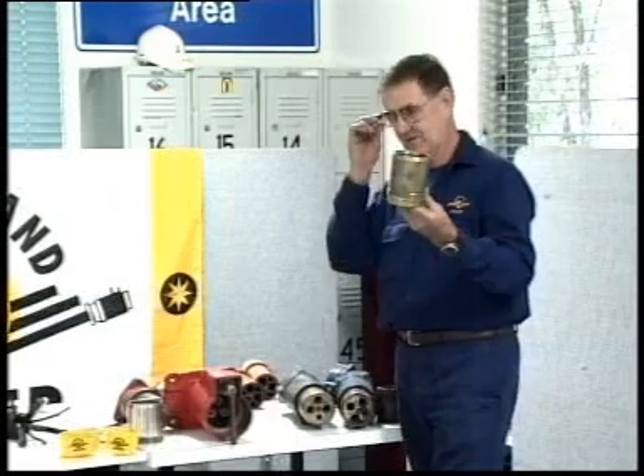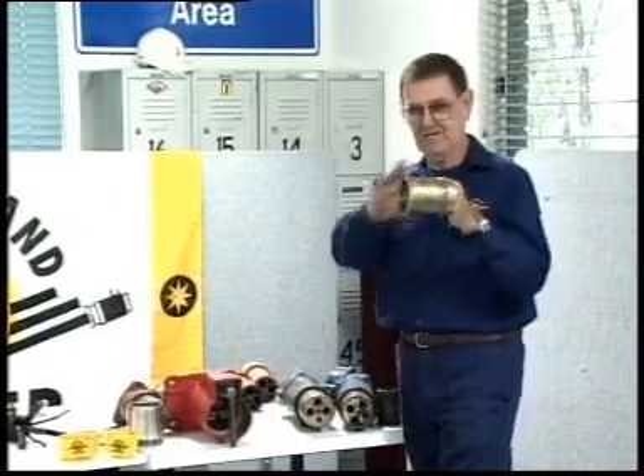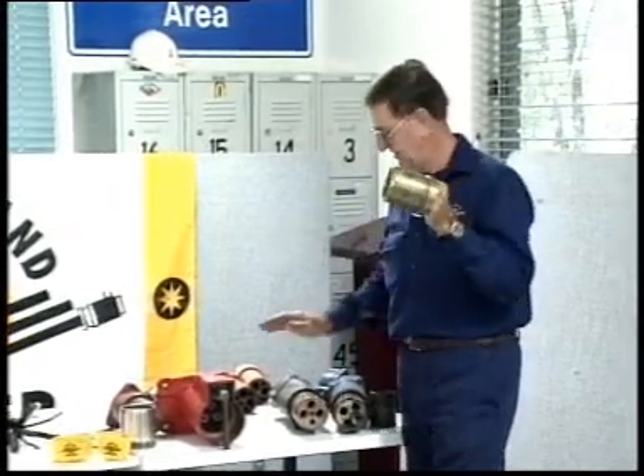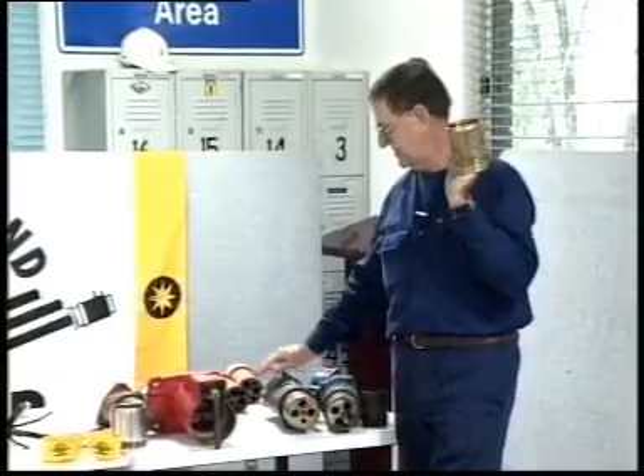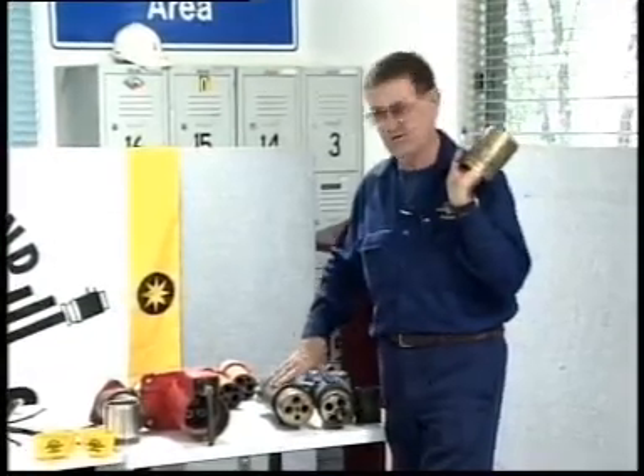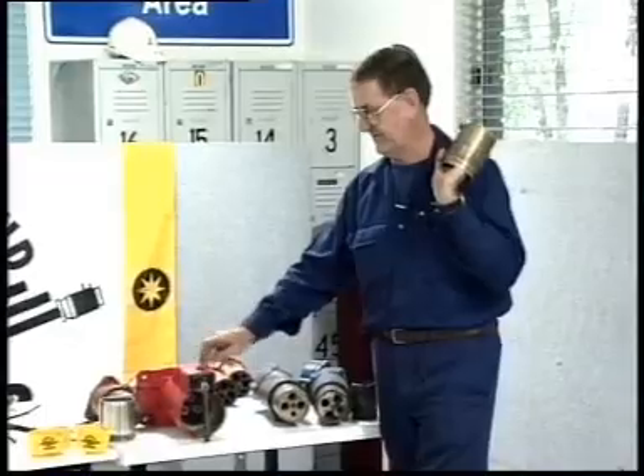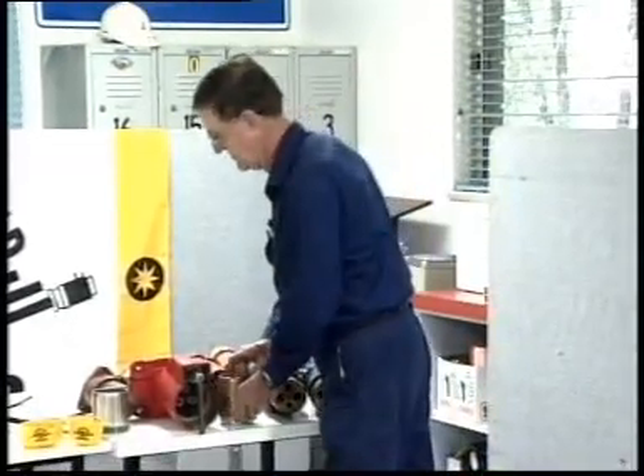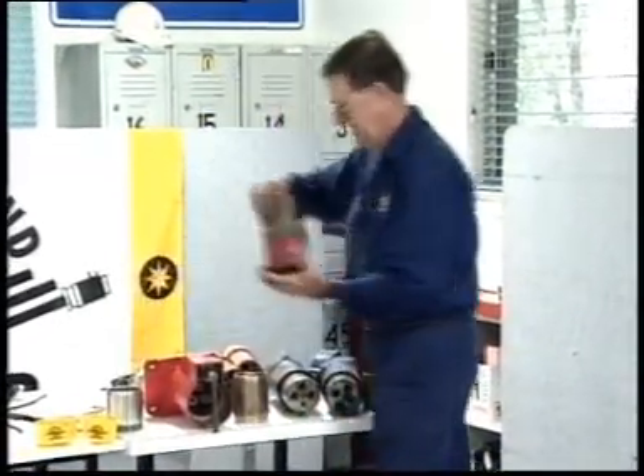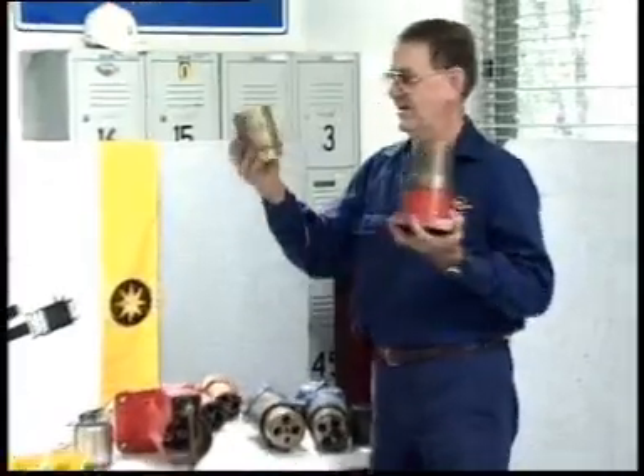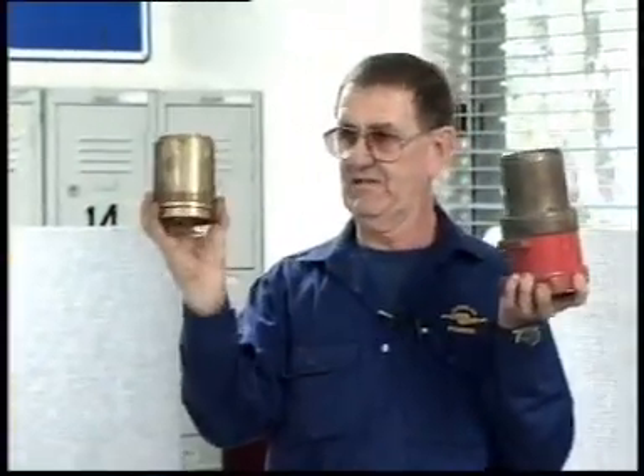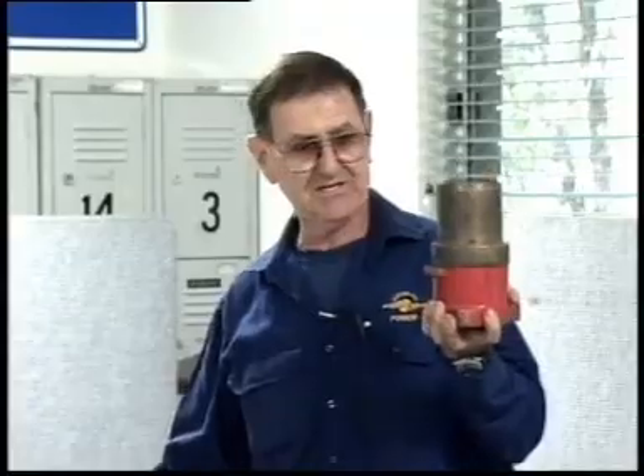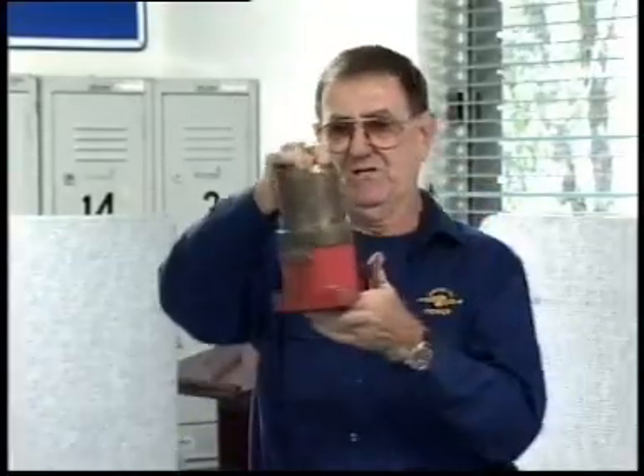This is the earth sleeve or earth skirt, and don't forget we said that was all the flame path of the plugs that you use in underground. The ones I've got here are 1000 volt, they're painted blue, and the red ones are 3300. There's a couple of different styles of plugs you can get. You can get them with an earth skirt or nose cone, some people call it, like that one there, or you can get them in one piece like that there. It depends on the type of plug that's being used.